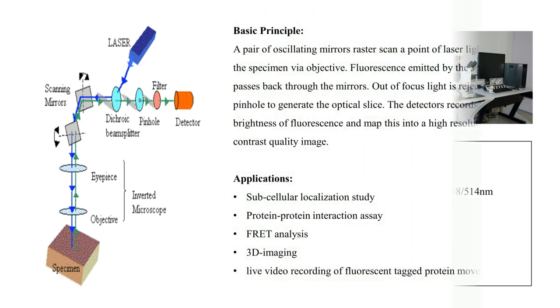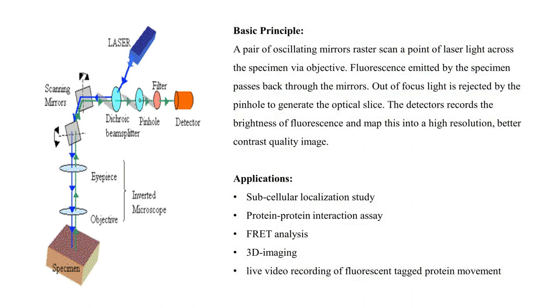The basic principle of the confocal microscope is that a pair of oscillating mirrors raster scan a point of laser light across the specimen via the objective. The fluorescence emitted by the specimen passes back through the mirror system to a beam splitter, which rejects any reflected excitation wavelength, and then through the pinhole to generate an optical slice. The detector records the brightness of fluorescence at each raster point and maps this into a high-resolution, high-contrast image.